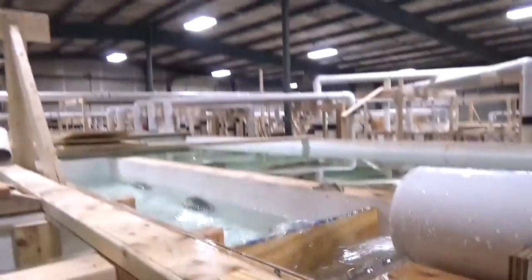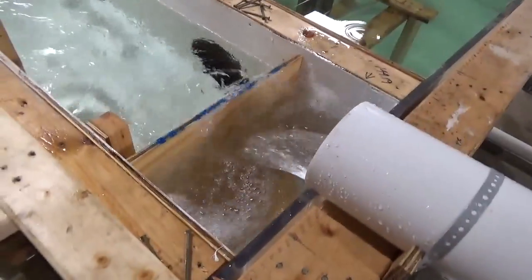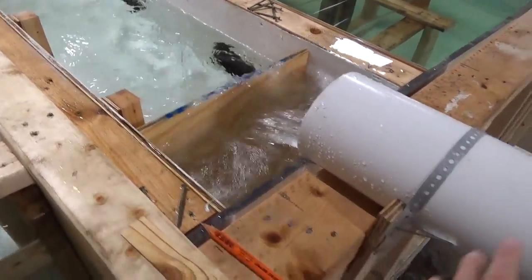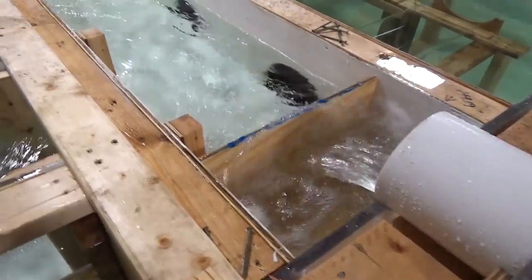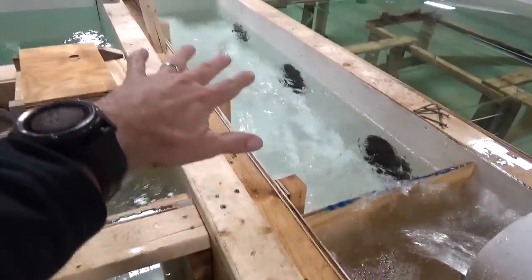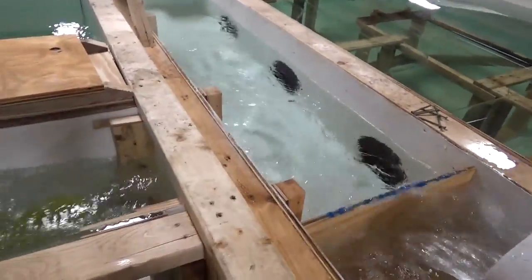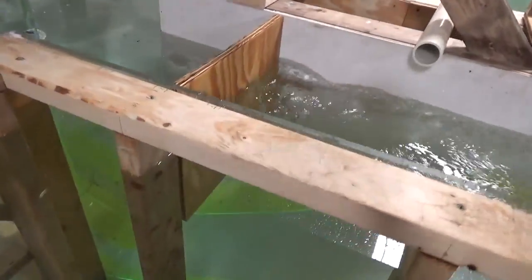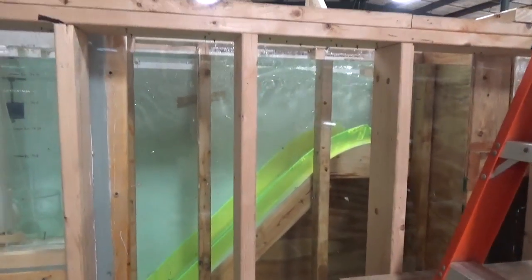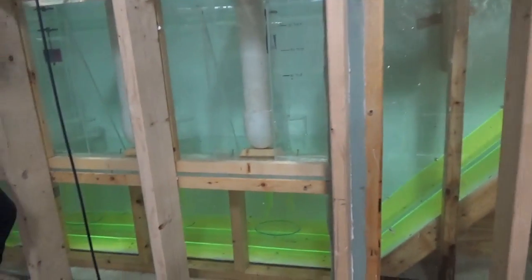Again, we've got a baffle box out here. We've looked at it up to 11,000 GPM. Originally we mentioned 8, but we tested up to 11. We just don't see benefit in adding additional baffling out there. We do have our trip blocks again here. So that's just some short video showing how this looks with modifications in place. We'll be having a witness test and demonstrating some other scenarios.